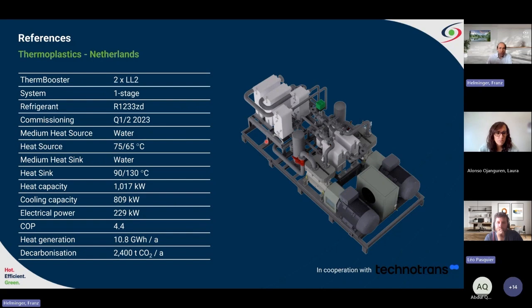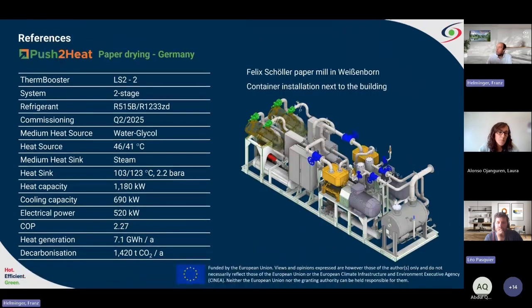Next, I will show you the graph of the design of the Push2Heat heat pump. There we decided, due to a higher temperature lift, so you can see here we have an inlet of around 46 and outlet 41 degrees C, and generating steam of around 2.2 bar absolute, so around 120 to 123 degrees C. There is a higher temperature lift.